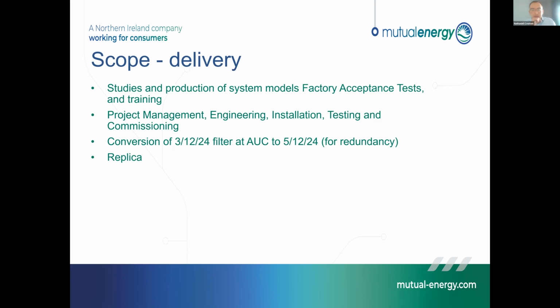Here's the next page. In terms of what that means, beyond just the equipment, there's a huge number of studies looking at how that network's changed on both sides, and production of system models for the TSOs. There's factory acceptance tests and training associated with the design as well. Obviously, it covers project management, engineering, installation, testing, and commissioning. Whilst we've got the outages, we're also going to convert one of the filters at Auchencross to a slightly different harmonic profile, just to provide some redundancy. And as I mentioned, we've got a replica as part of this upgrade.